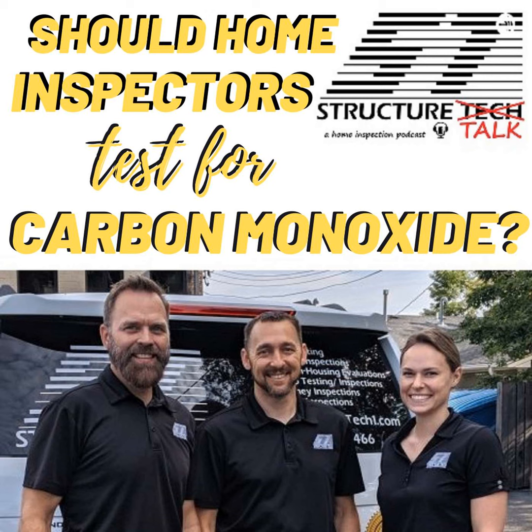And you know what? There's one other thing we didn't touch on. We talked about the 400 threshold, but what about if it's 300? Is that okay? Really, no. You talk to pretty much any heating contractor and they're going to tell you it's not burning properly when it's that high and you've got a problem.